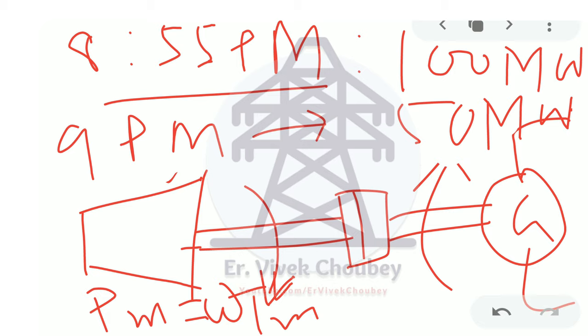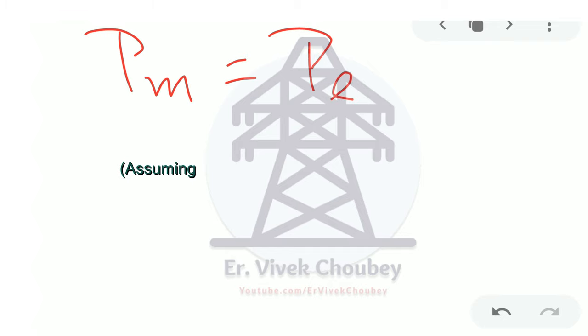So what is the problem if all this is unknown? At 8:55 p.m., what is happening? The steam that the controller is providing to the turbine is equivalent to that required for 100 megawatt power generation. That means the mechanical power is very high, and that mechanical power is equivalent to 100 megawatt. Now, the simple rule that is followed in a power plant is that PM must be equal to PE.